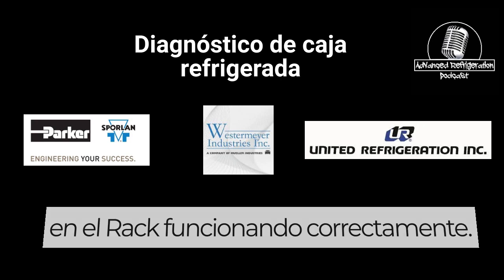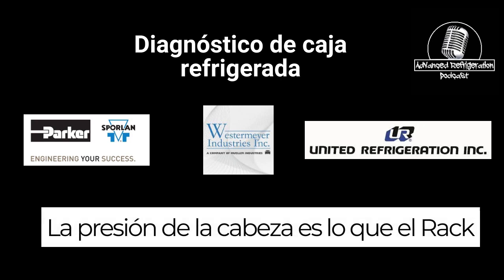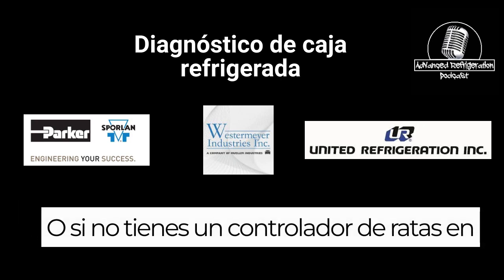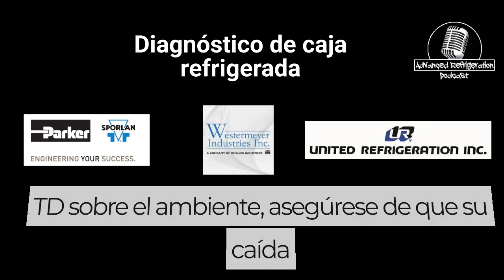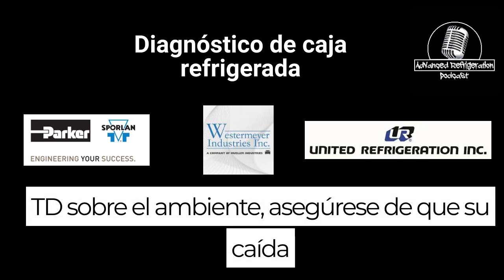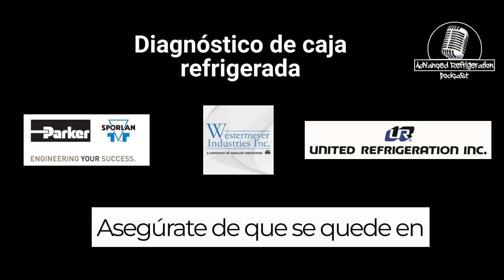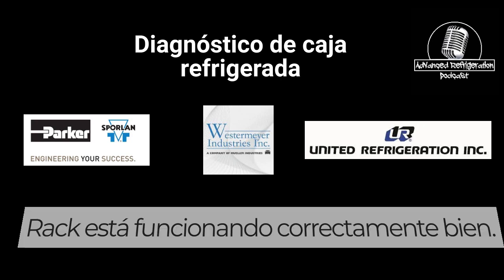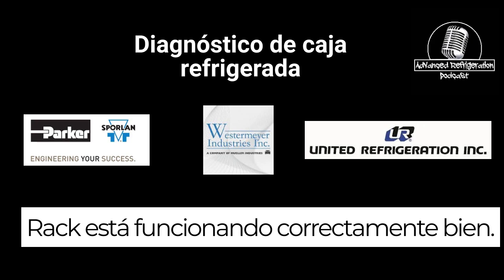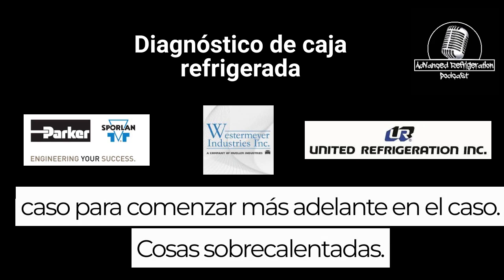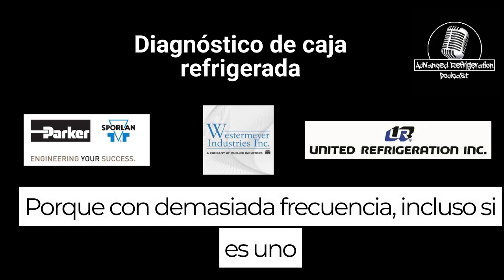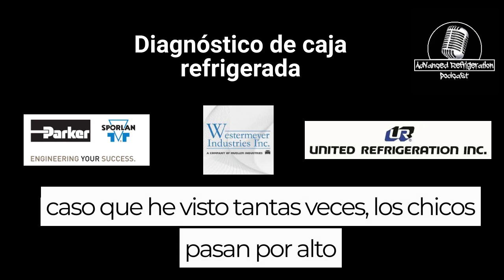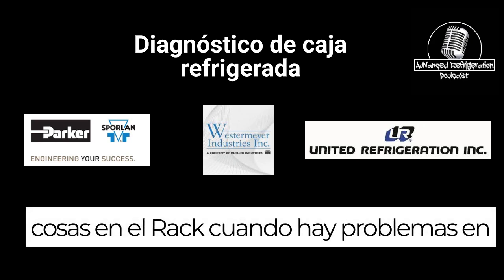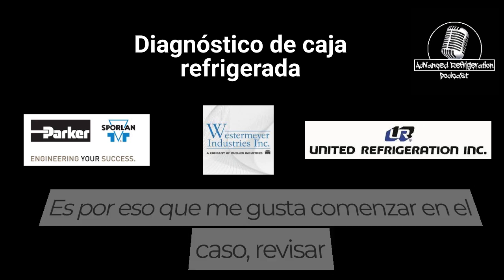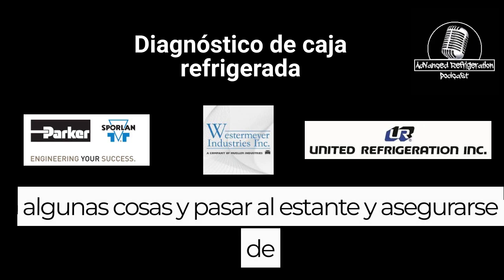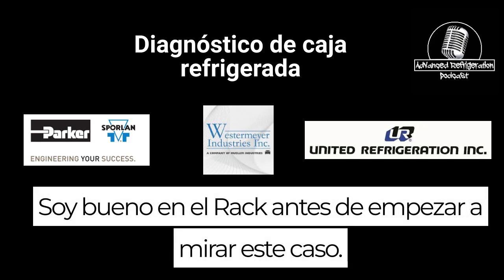So I like to see everything at the rack running properly. Head pressure is at what the rack controller says it's supposed to be. Or if you don't have a rack controller, at TD over the ambient, make sure that your drop leg pressure is not dropping too low. Make sure that that's staying at what it's supposed to be. Make sure everything at the rack is running properly and good before I move on back down to the case to start checking further into the case, superheats and stuff. Because, I mean, all too often, even if it's one case, I've seen so many times guys overlook things at the rack when there's issues at the rack and they're missing the big picture. So that's why I like to start at the case, check over a few things, and move on to the rack and make sure I'm good at the rack before I start looking at this case.